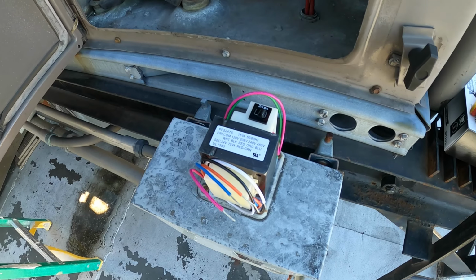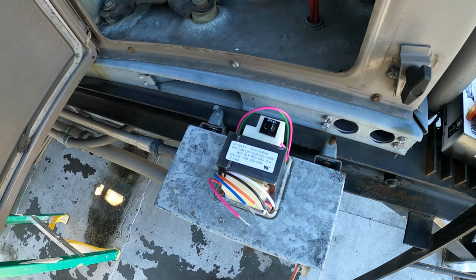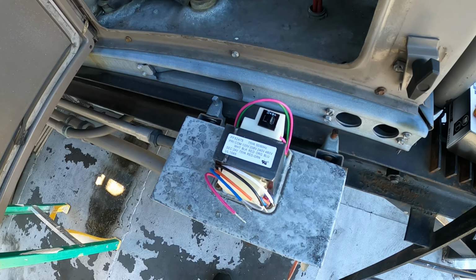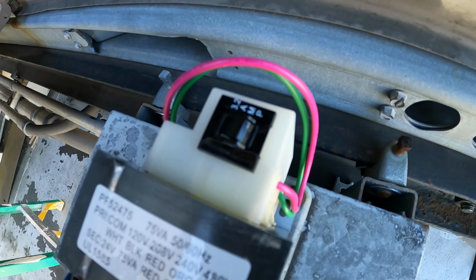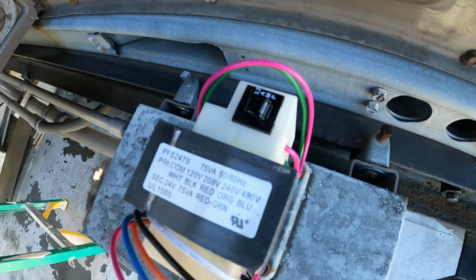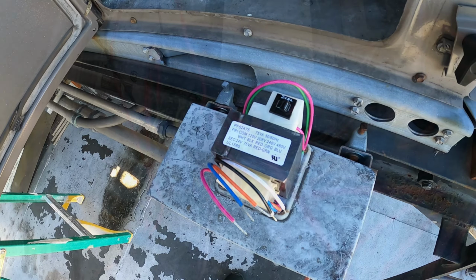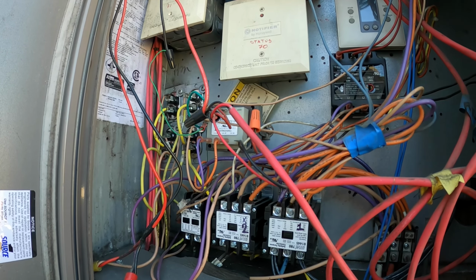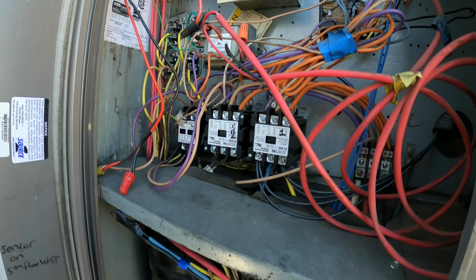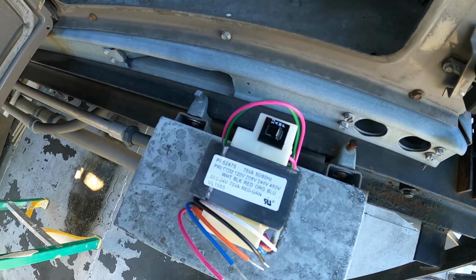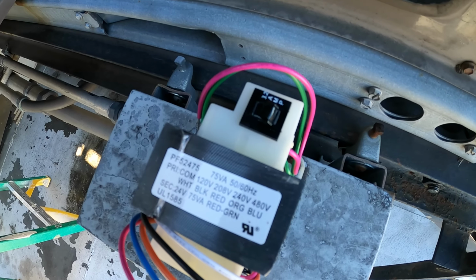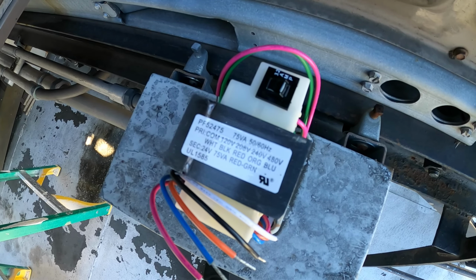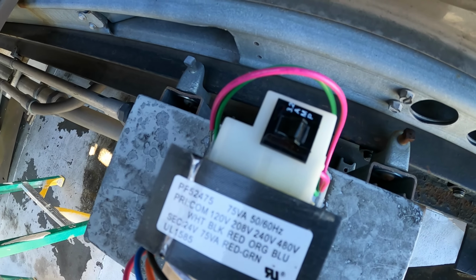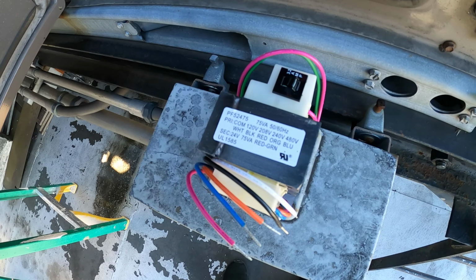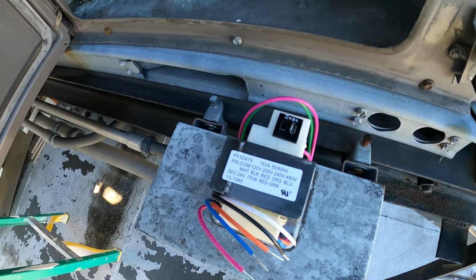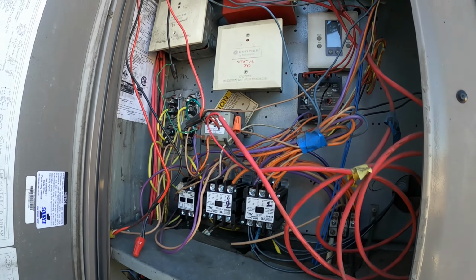This one here is a universal transformer, but how is it an upgrade? It's an upgrade because, if you can see right here, we have a built-in 3.2 amp breaker which protects the low voltage circuit. We had a short here, and what happened, the transformer burned out. If there happens to be a short in the future, in this case, you have a breaker, so instead of it burning out the transformer, it's going to trip the breaker. So anytime you change the transformer, try to pick one up that has a built-in breaker in it, because that is totally worth the investment.